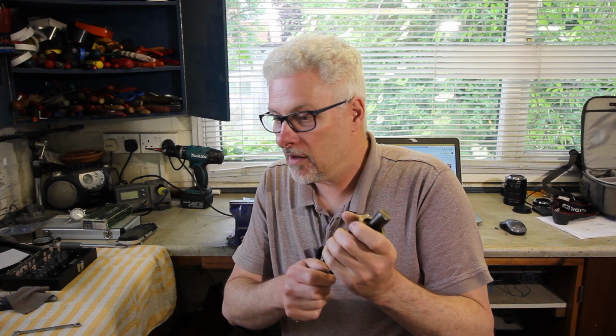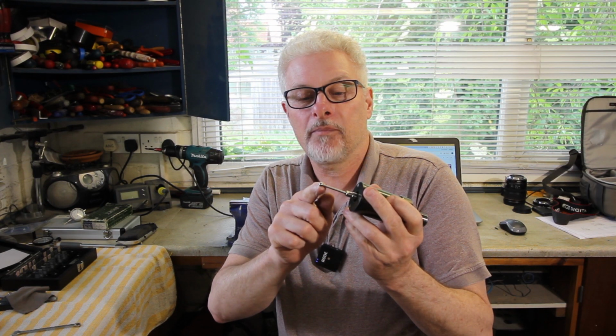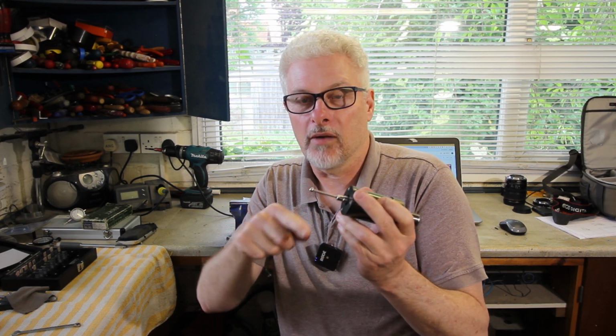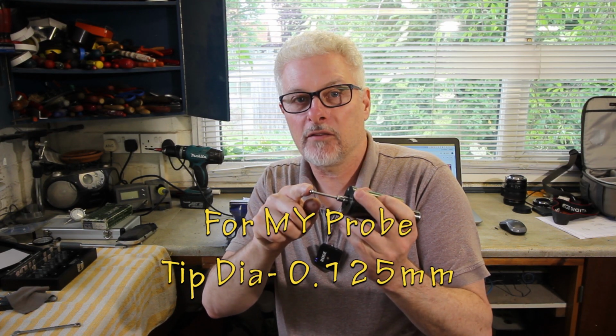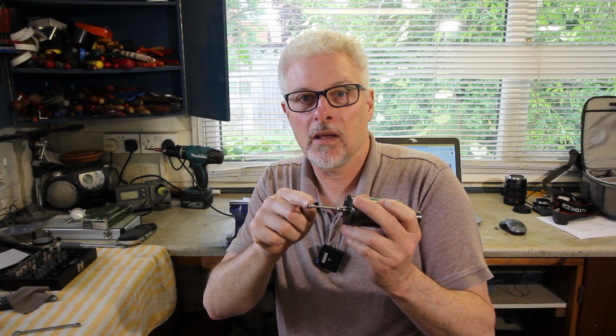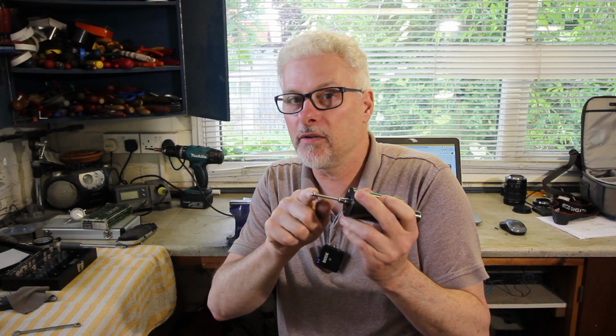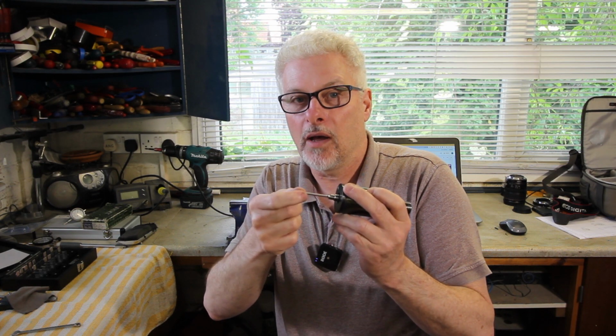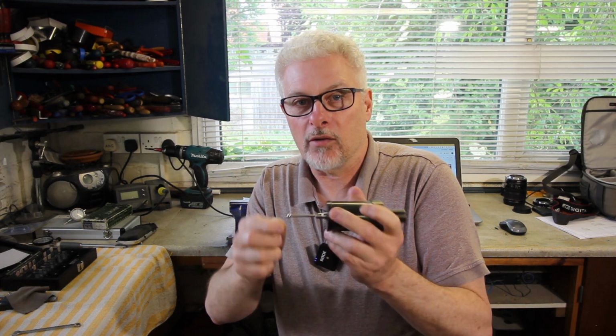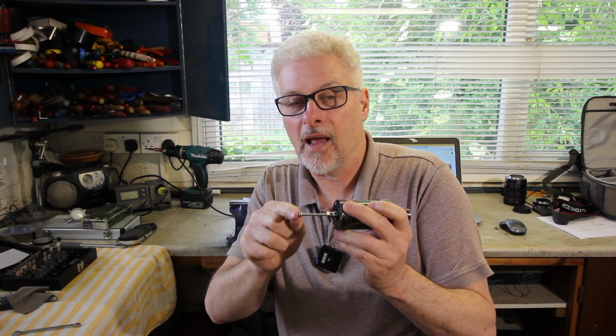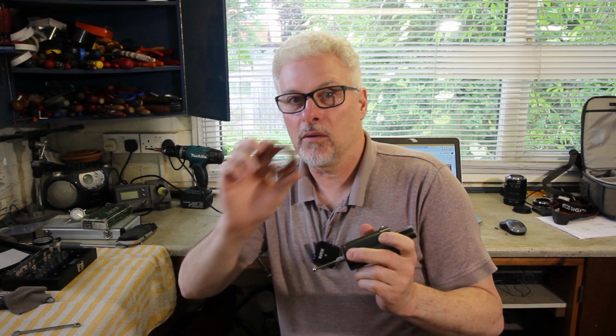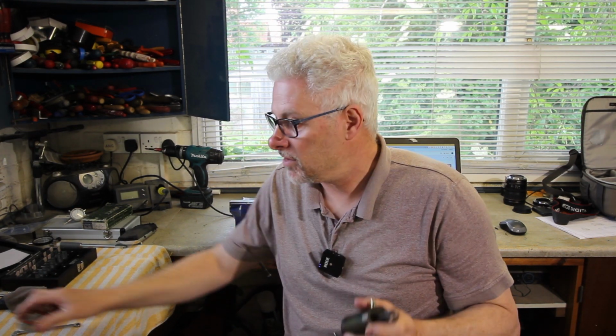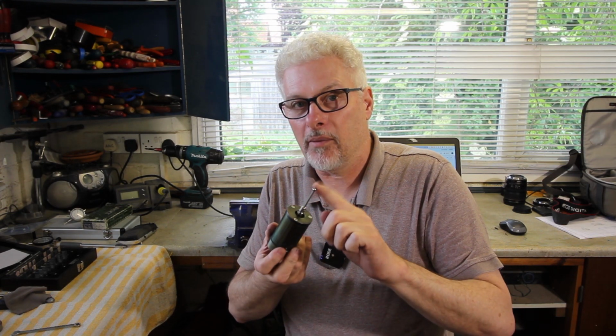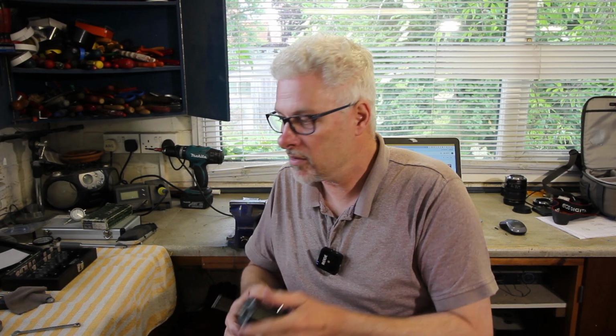The other thing is, I think the ball on the end, what I'll do is work out, in fact I'll put it as an overlay, the diameter of the ball with the correction factor that you'll need to apply. So if you use a ball of a different diameter on another probe, you know what you need to add or subtract to the diameter of the ball in order to make it read accurate again. That means that you won't have to get your old gauge ring out and test it each time, and you won't need to do the plunge test that you've just seen me do on the Z-axis. So you should just be able to put it in, check for run out, and adjust for run out, and you should be good to go.